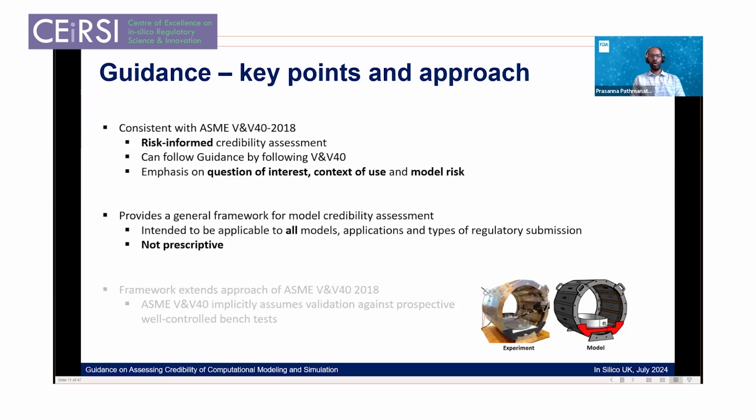The guidance provides a general framework for model credibility assessment that's intended to be applicable to all models, at least all first principles models, not data-driven AI/ML, all applications, solid mechanics, fluid flow, electromagnetism, physiological modeling, and any kind of device-related question for any of those models, and all types of regulatory submission, whether that's for initiating a clinical trial, a 510K, or a PMA regulatory submission, if you know what those are. It's supposed to be applicable to all of these cases. And that means it's very general and not prescriptive.